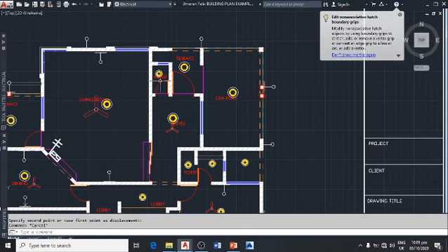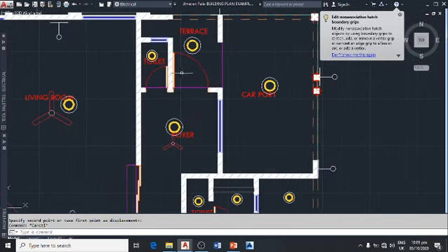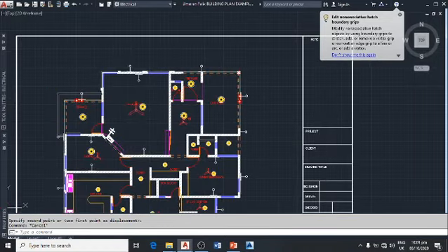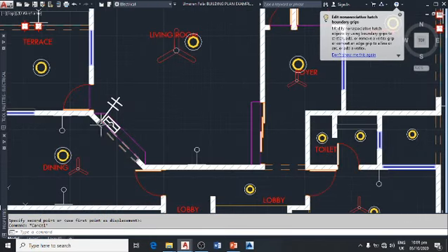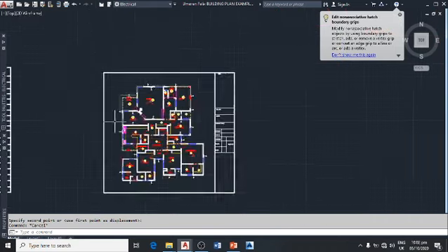So for the toilet, the switches will be outside the room. Then the others will be at the side of the door. The switches must be easily accessible. Once you're entering a building, the first thing you should be able to touch is the switch, whereby you can put on the light in the room before entering the room.